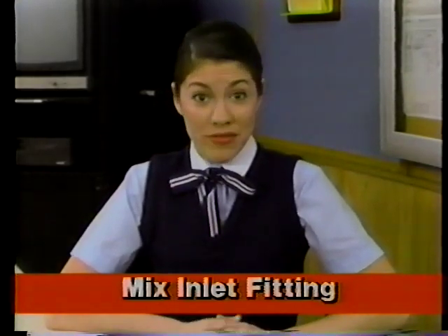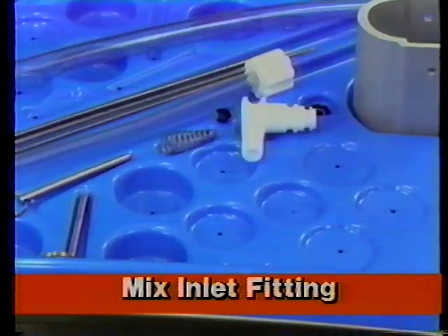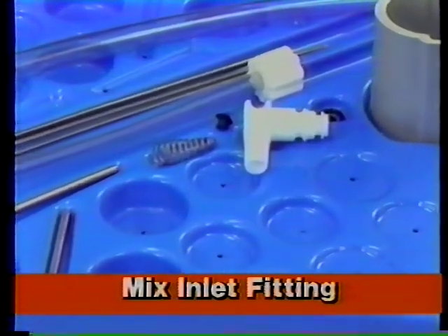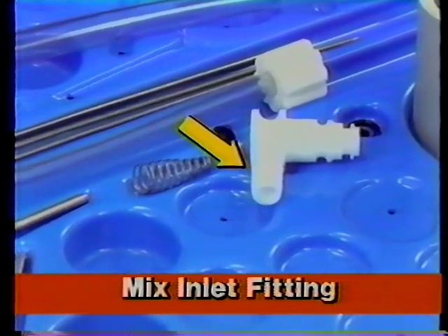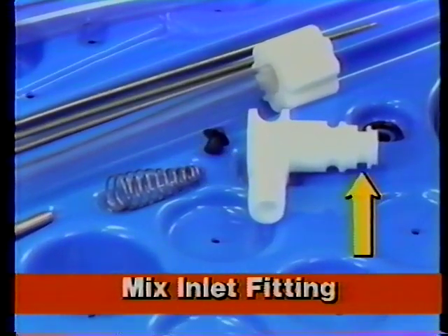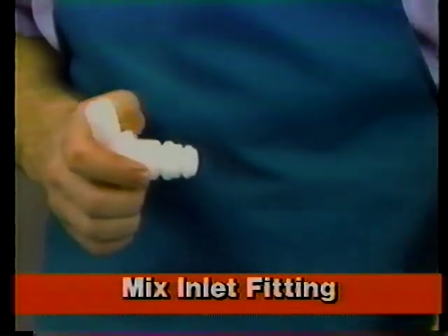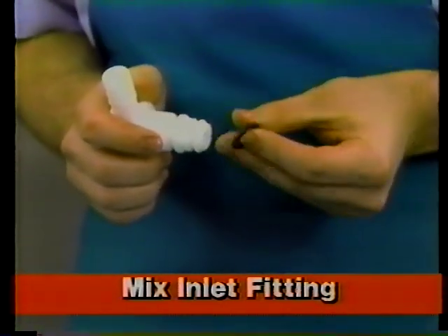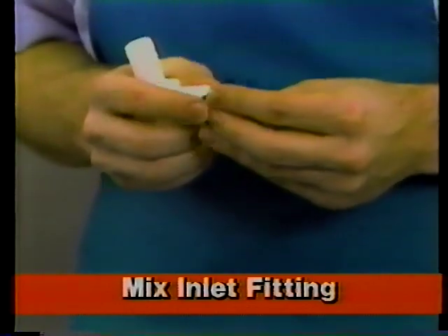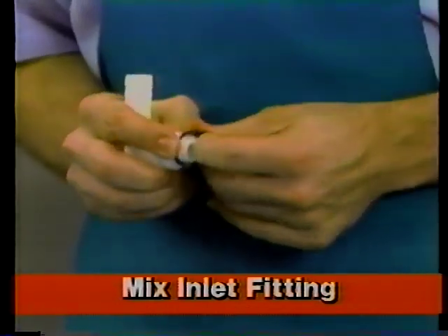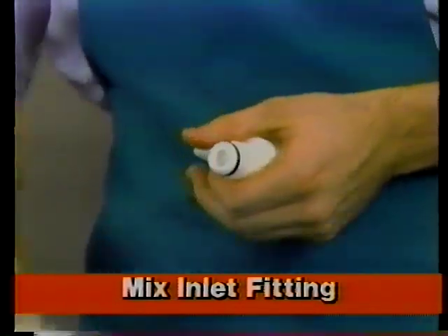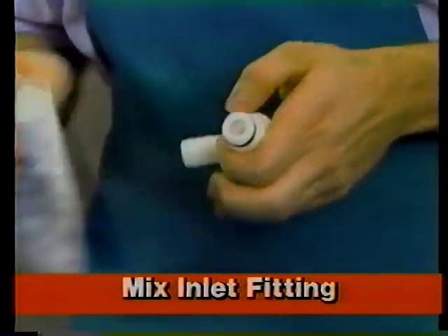Now, set the pump cylinder down for a minute and put together the mix inlet fitting. It's going to go on the bottom of the liquid valve body. It's an L-shaped part. It has barbs on one end and a groove for an O-ring on the other end. Check the O-ring for cuts or nicks, then slip it over the end of the fitting and into the groove. Then, thoroughly lubricate the fitting with Petrogel.